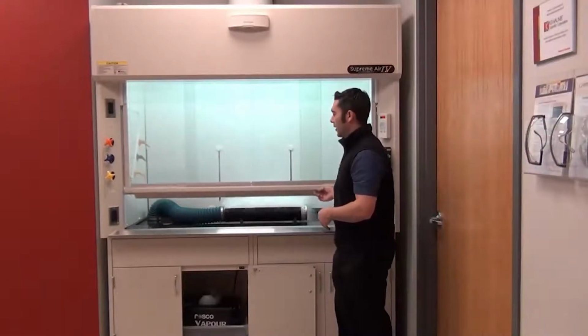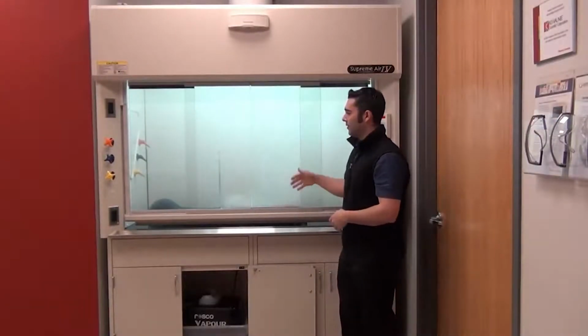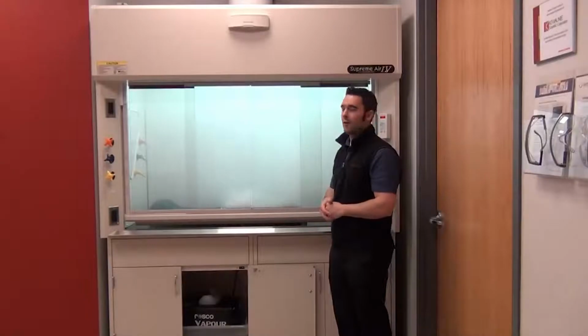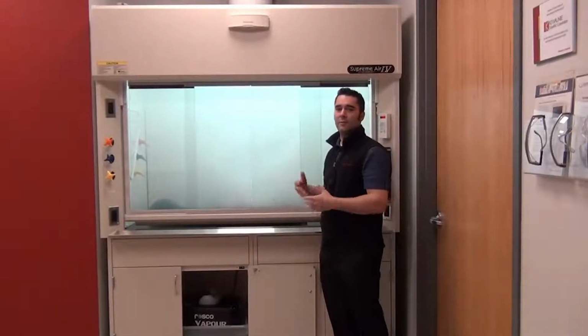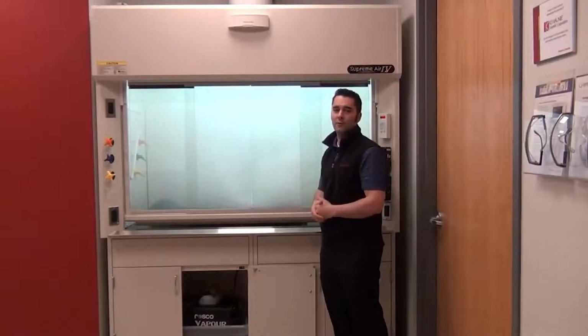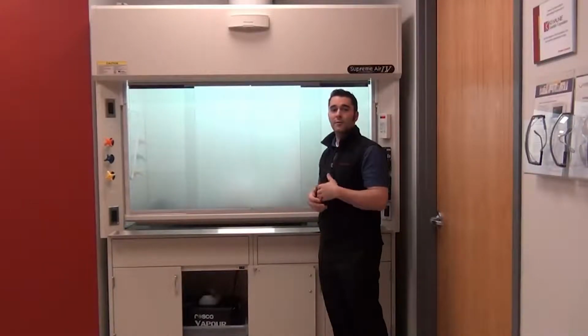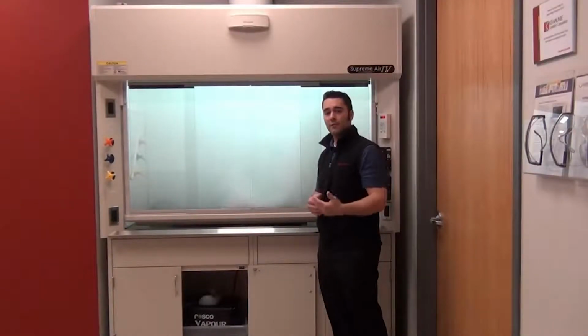So conversely, when I close the hood, you'll see the air is very turbulent inside of the fume hood, which is going to cause that same issue with mixing chemicals or things to get knocked over as well. So I showed you the difference between a 1 second speed of response, a 3 second speed of response, and a 6 second speed of response.